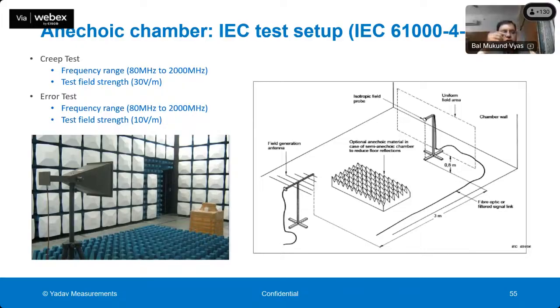So to test the immunity of the meter against this kind of radio frequency field, a special chamber is required, and a very expensive chamber. This type of chamber can sometimes cost around 5 to 8 crore of rupees, and it has an antenna. A picture of the inside of this chamber is shown here. You can see various blue conical shapes. They are actually radio frequency absorbers. This chamber is called an anechoic chamber.